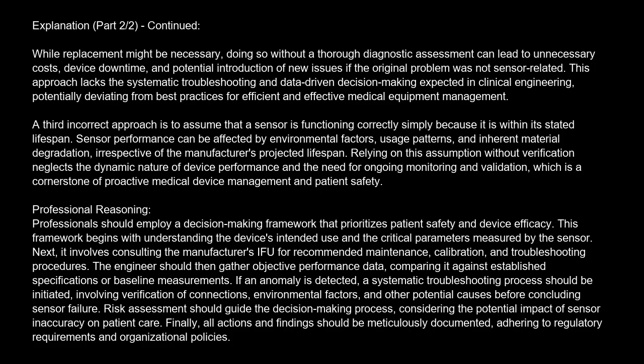If an anomaly is detected, a systematic troubleshooting process should be initiated, involving verification of connections, environmental factors, and other potential causes before concluding sensor failure. Risk assessment should guide the decision-making process, considering the potential impact of sensor inaccuracy on patient care. Finally, all actions and findings should be meticulously documented, adhering to regulatory requirements and organizational policies.